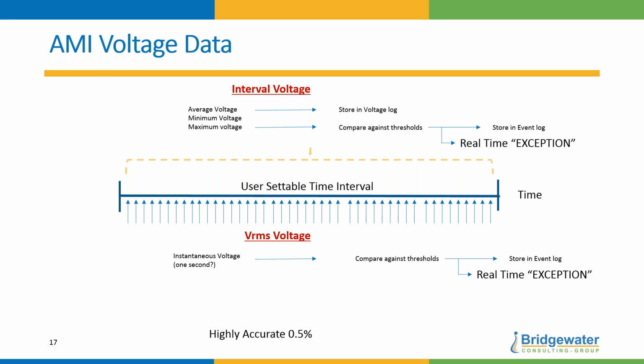Now, the meters can also look at voltage continuously. We call it VRMS voltage. You can set it for 1 second, 3 seconds, but every second the meter will look at the RMS voltage and compare it against thresholds. This is 1 second values. That's pretty good. It's not a power quality meter, you know, the cycle analysis, but it can do pretty short interval kinds of measurements. The cool thing is, it'll compare it against thresholds, and if it exceeds, it'll store it in the event log, but it can also send out a real-time exception. So on a 240 volt meter, you say, hey, whenever it drops below 180 volts RMS for 1 second, it'll send out an exception. So that becomes very powerful in the way of using this data for distribution.